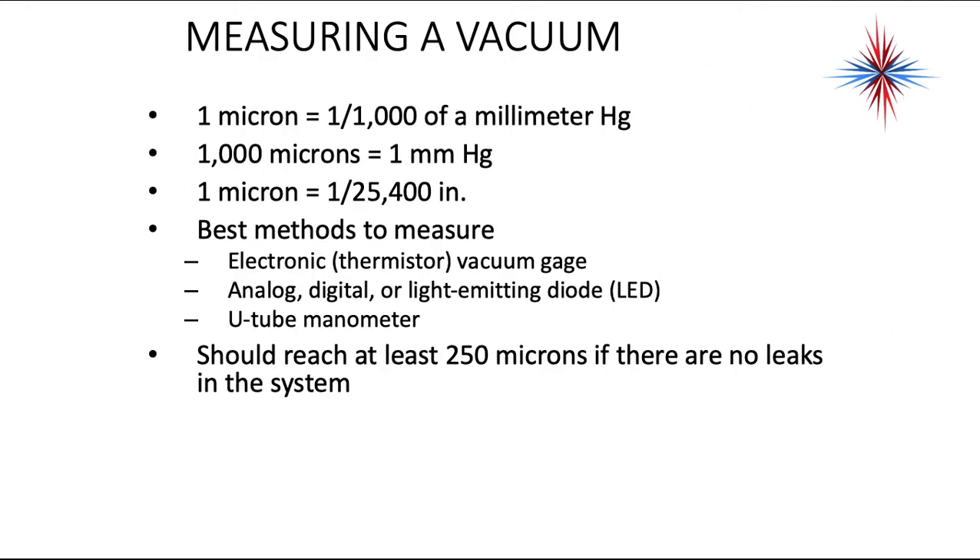When we talk about measuring a vacuum, one micron equals one one-thousandth of a millimeter of mercury. One thousand microns equals one millimeter of mercury. One micron equals one twenty-five-thousand-four-hundredths of an inch of mercury. The best method to measure a vacuum is an electronic vacuum gauge — analog, digital, light emitting diode, or U-tube manometer. You want to use an electronic vacuum gauge that measures microns. Some of the new gauge sets actually have these built in, which is really nice.